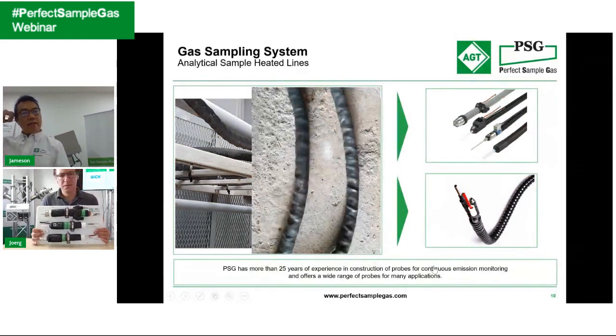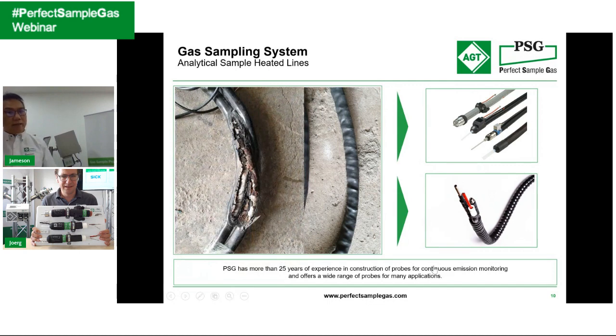Yeah, and this photo was taken by me. When you say heated line, you always mention it is the most underestimated sampling component. Yeah, it is, because this is a black hose. Nobody really knows what's inside. So this is another photo that I've taken at site. You look at the jacket and the exterior of this, you can see how badly it was designed and then constructed. You can see the skeleton and the bad insulation, the way they wrap it. And this is also taken at site. In fact, because of the overlapping, the over temperature, it caused a fire. It burns out.